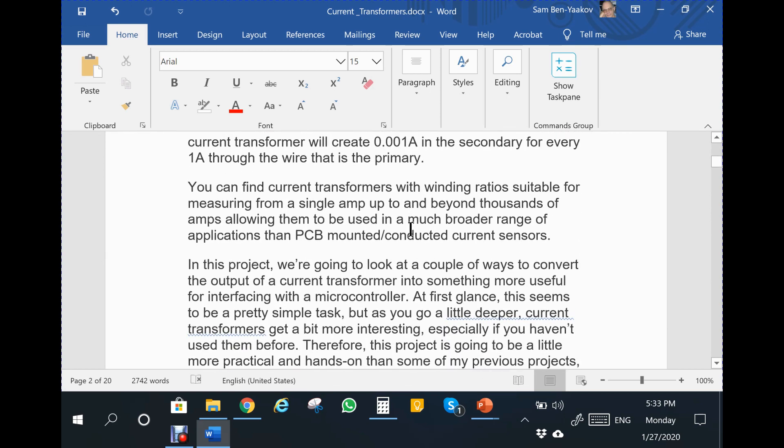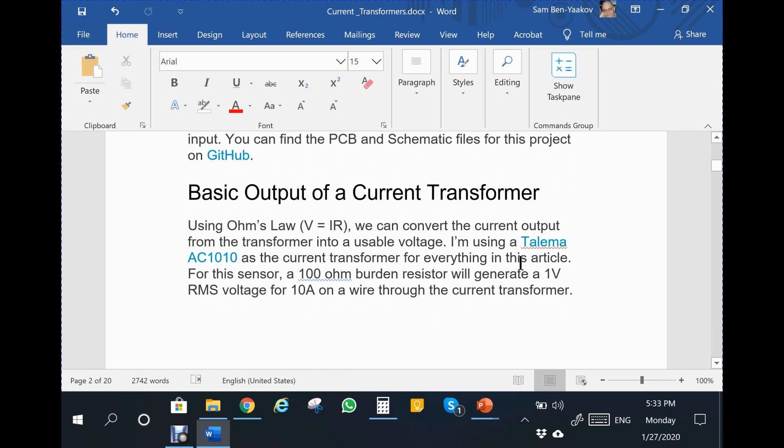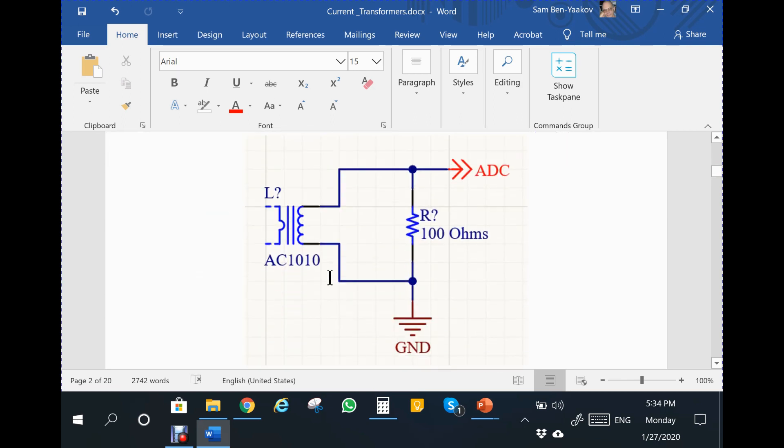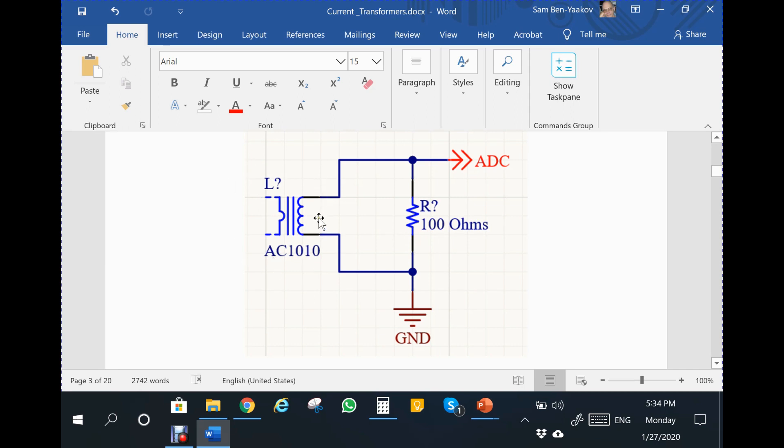Here it is within the Word document. This project has to do with measuring current via a current transformer. The current transformer being used is the Talema AC1010, which is used as a current transformer with a one to one thousand turns ratio, loaded by 100 ohms. One amp divided by a thousand will be one milliamp, then times 100 will be 0.1 volt per one amp.